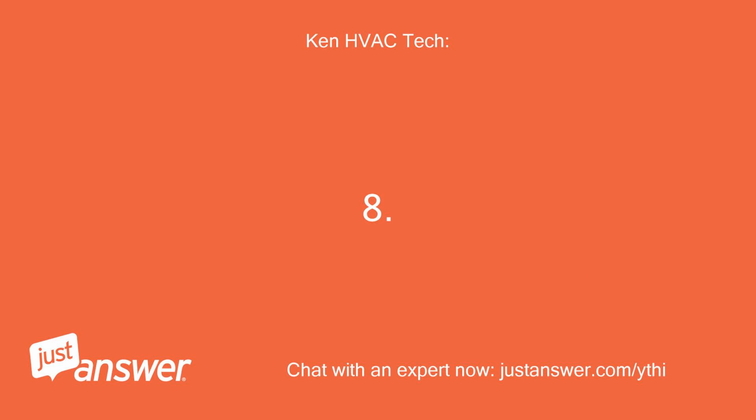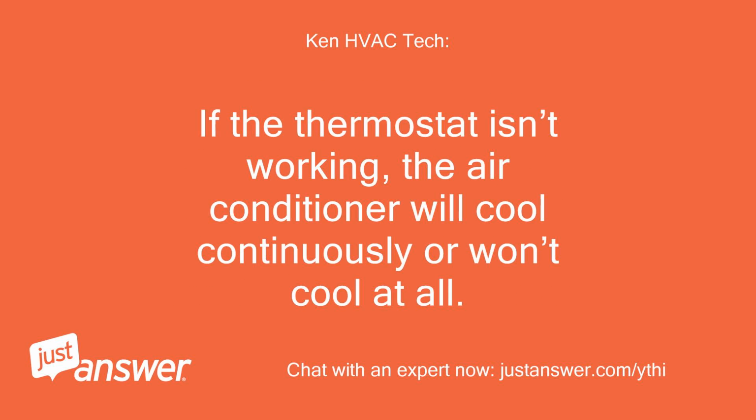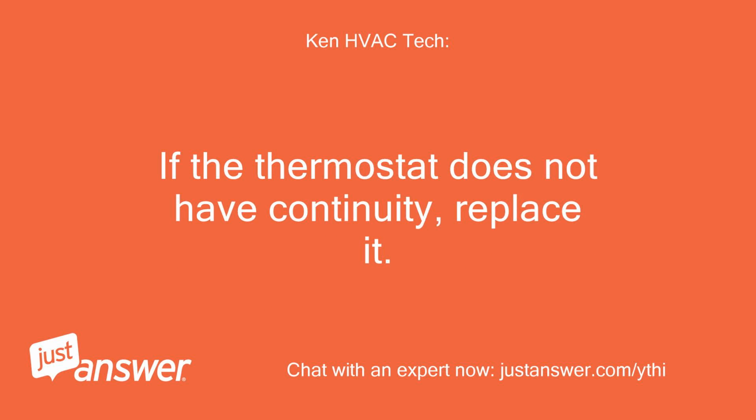8. The temperature control thermostat is a sensor which monitors the temperature of the air and activates a switch to provide power to the fan and compressor when the air temperature drops below a set point. If the thermostat isn't working, the air conditioner will cool continuously or won't cool at all. To determine if the temperature control thermostat is defective, use a multimeter to test it for continuity. If the thermostat does not have continuity, replace it.